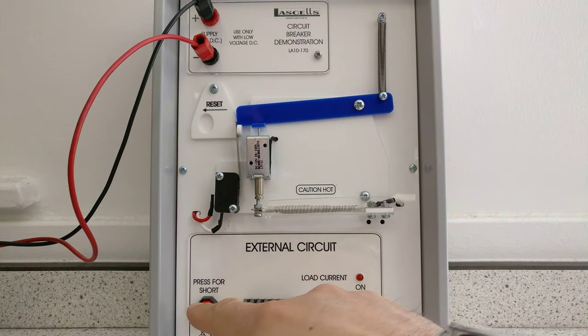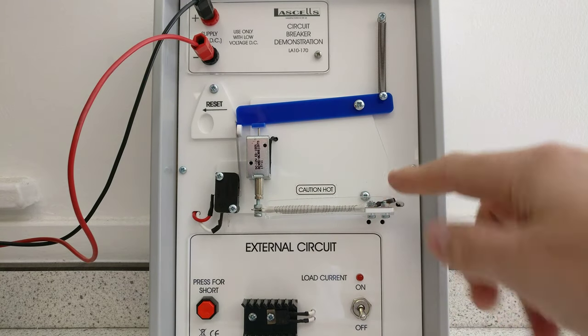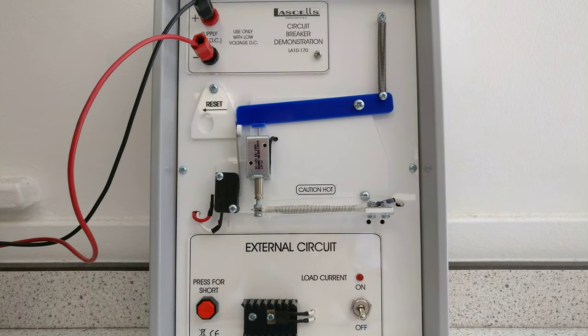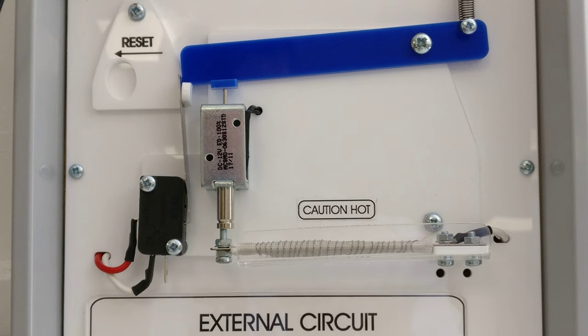I can press for a short circuit down here and when I do that you should see this actuator arm move and the magnetic field come on, or we can leave it for a while after switching it on and watch this slowly curve up. The power comes in here, I've got a reset button, but all the exciting action happens at the top so I'm going to zoom in just to the main part so you get a really good view.